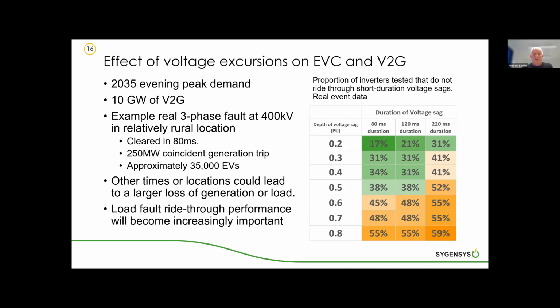But from the estimates of the current performance of grid-connected inverters, we would anticipate that during an incident of that type, we might see up to 250 megawatts of generation trip. So 250 megawatts of V2G. And that's considering that particular example in a rural location. If we looked at a city and considered a major 3-phase fault in the centre of London, potentially we might end up with much higher levels of coincidence loss.